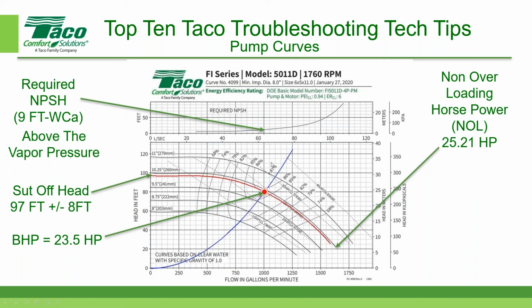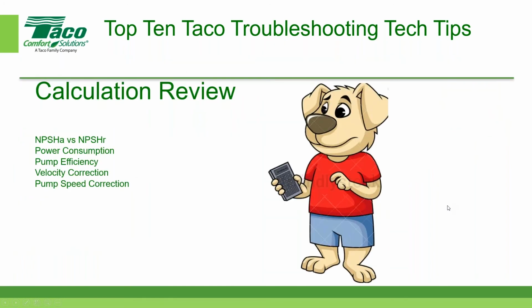And then the last thing that we can get from the pump curve is the net positive suction head required by the pump. In this case, it's approximately 9 feet of water column. And again, the units for net positive suction head required by the pump is 9 feet water column absolute. So these are absolute pressures up here. So I have more information. That's how I was able to collect all that data. All right, let's move along here.